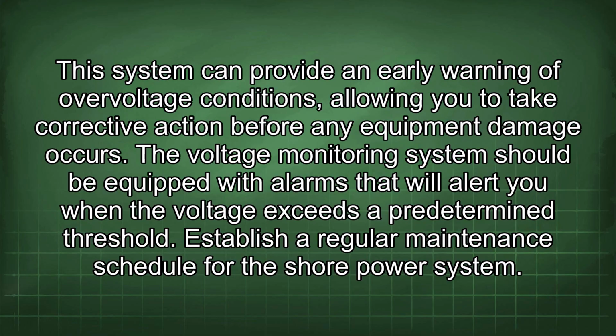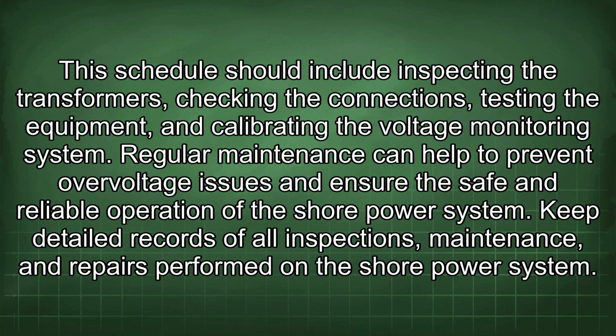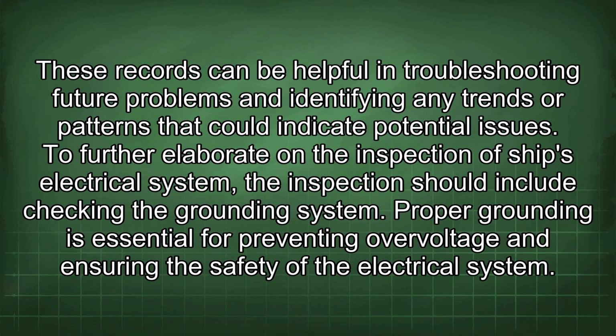occurs. The voltage monitoring system should be equipped with alarms that will alert you when the voltage exceeds a predetermined threshold. Establish a regular maintenance schedule for the shore power system. This schedule should include inspecting the transformers, checking the connections, testing the equipment, and calibrating the voltage monitoring system. Regular maintenance can help to prevent overvoltage issues and ensure the safe and reliable operation of the shore power system. Keep detailed records of all inspections, maintenance, and repairs performed on the shore power system. These records can be helpful in troubleshooting future problems and identifying any trends or patterns that could indicate potential issues.